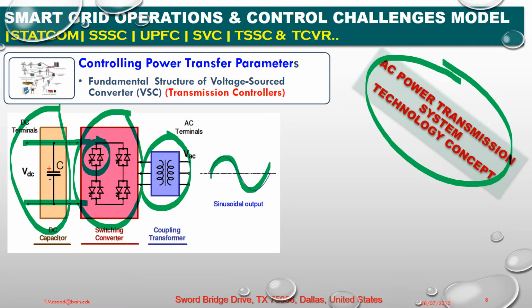Okay, this capacitor is large enough to at least sustain the charge and discharge current that accompanies the switching sequence of the converter valves and shift in phase angle of the switching valve without significant change in the DC voltage. The DC capacitor voltage will be assumed constant.